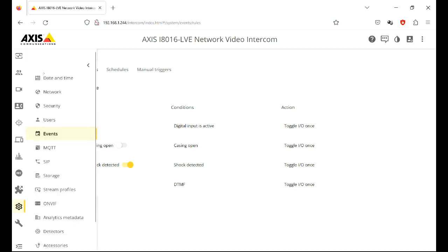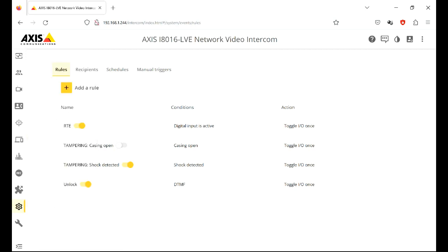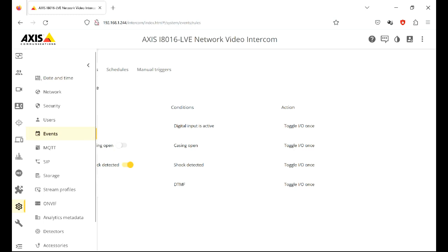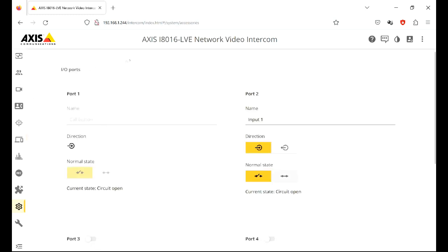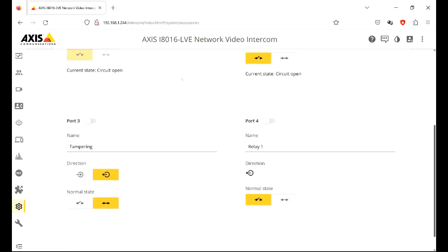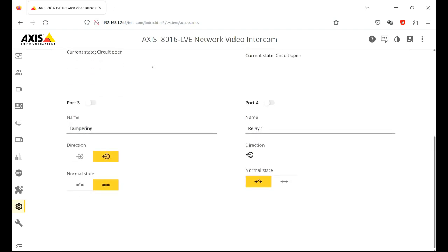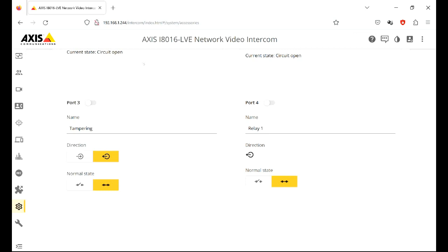Go to settings. Again, scroll down to accessories. These are your port, your port outputs. Scroll down port four, which is relay one. Its normal state there, as you can see, it's normally open. If you change it to normally closed, the output's now normally closed. So you could run a mag lock, a fail safe device through that relay, and the circuit will be broken when you make a valid exit or release request from the handset.